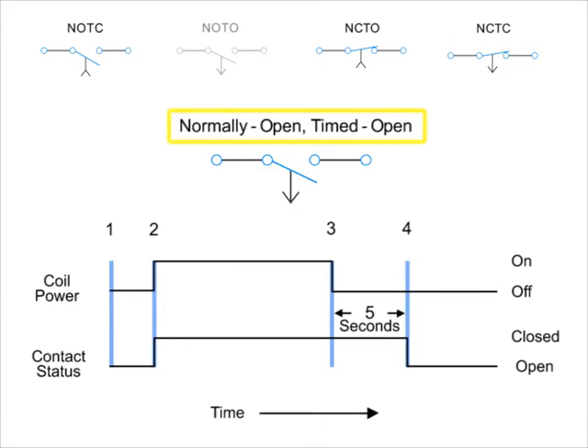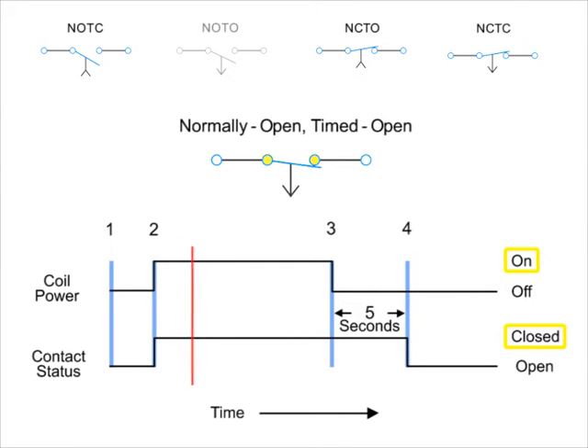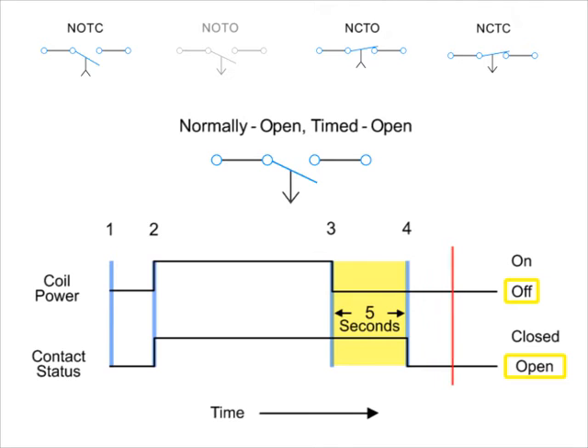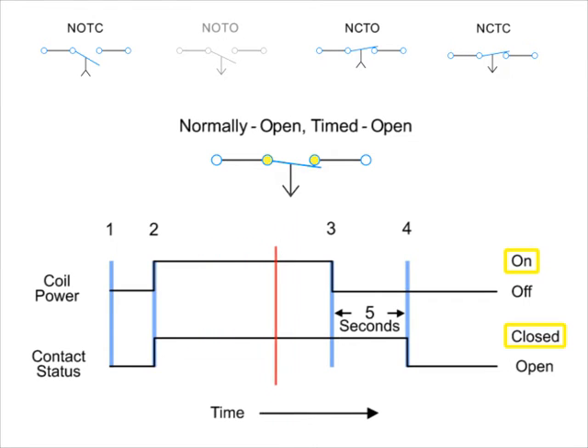Next, we have the normally open, timed open contact. Similar to the normally open, timed closed contact, this type of contact is normally open when the coil is unpowered or de-energized, and closed by the application of power to the relay coil. However, unlike the NOTC contact, the timing action occurs after the coil is de-energized for five seconds. Thus, the contacts close immediately when the coil is energized and open five seconds after the coil is de-energized.